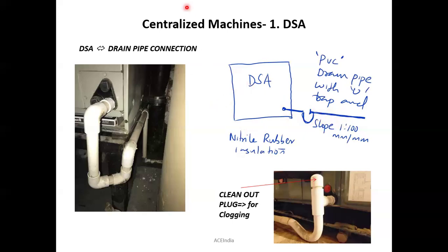At the same time, with the U-trap the fan needs more energy to draw the water. But if it is a straight pipeline, the fan can easily pull the water from the pipeline itself, isn't it? That is the purpose of installing U-traps across the system, especially on the drain line. Okay, Shamir, clear?